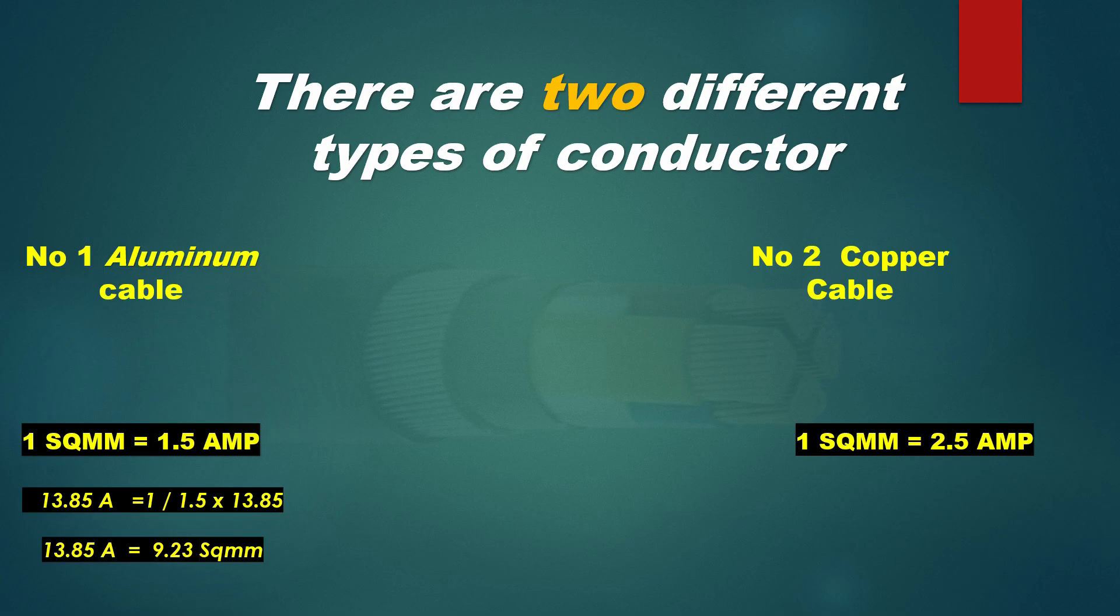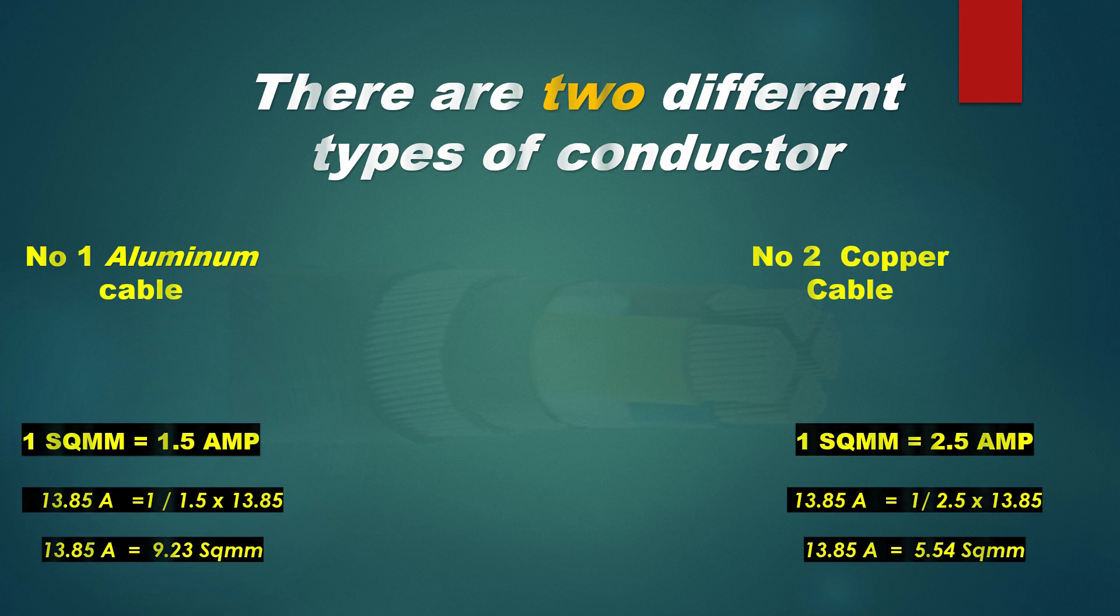Now, 1 square mm is equal to 2.5 ampere. 1 divided by 2.5 multiplied by 13.85 is equal to 5.54 square mm.